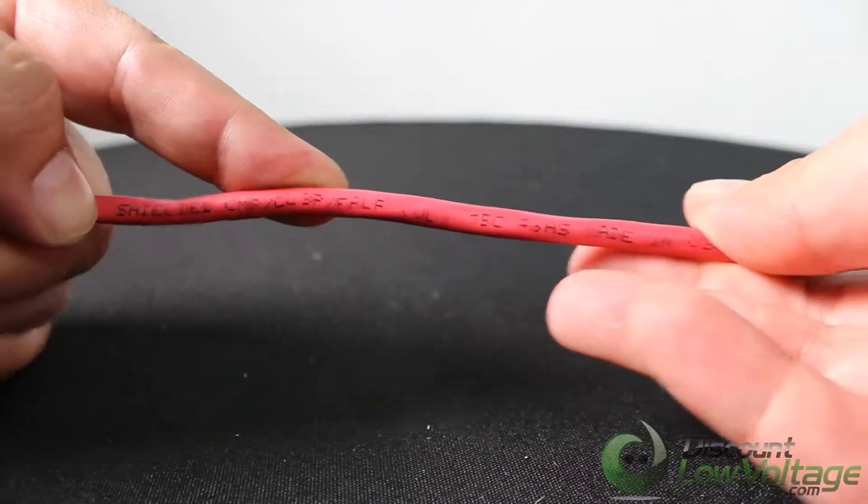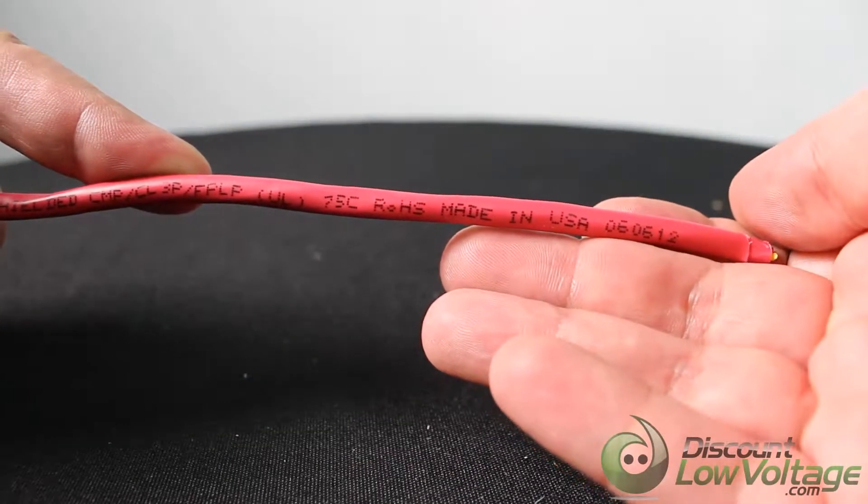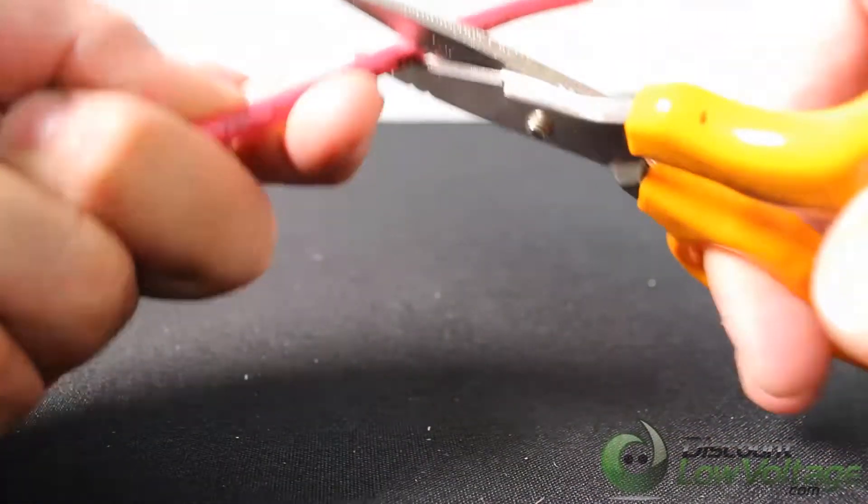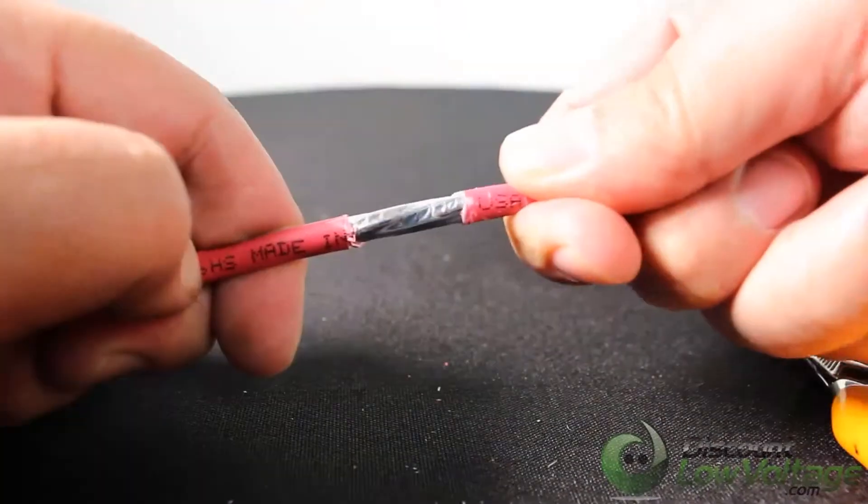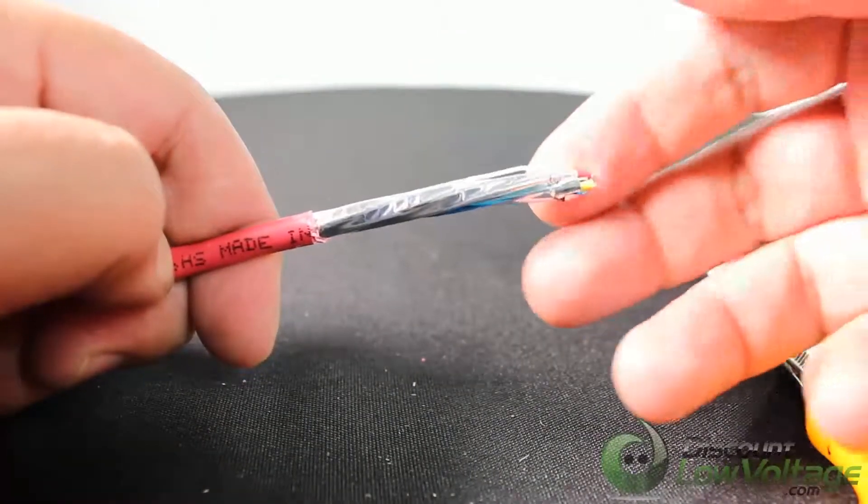All plenum-listed fire alarm cables provide compliance to NFPA Article 760, NFPA Article 725, FPLP, and CL3P. These are rated for power-limited 300 volts.